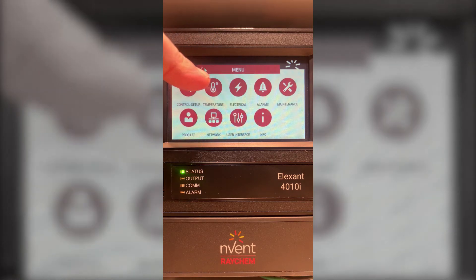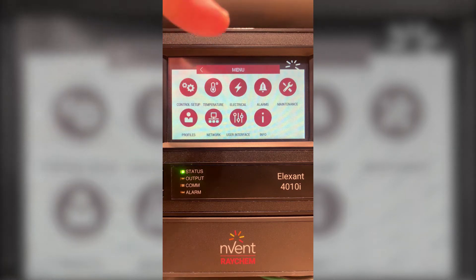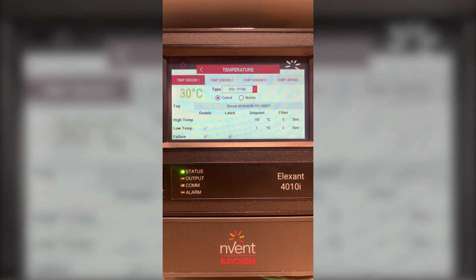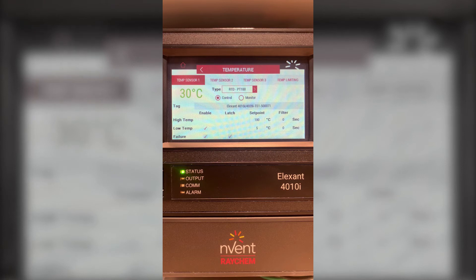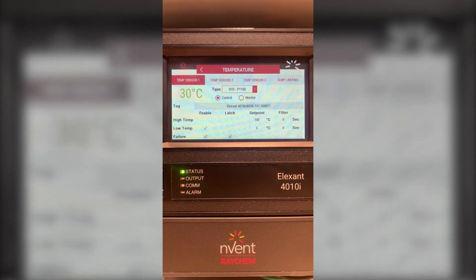Going back to the main menu I will now choose temperature. In the temperature you'll have temperature sensor 1, temperature sensor 2, and temperature sensor 3. In this case I only have one RTD connected therefore I will only stay on temperature sensor 1. At the moment it's displaying 30 degrees Celsius. Each temperature sensor can be set to control or monitor only. Also each RTD can have a high temperature alarm, low temperature alarm, and failure alarm. These can be enabled or disabled and latching and non-latching.